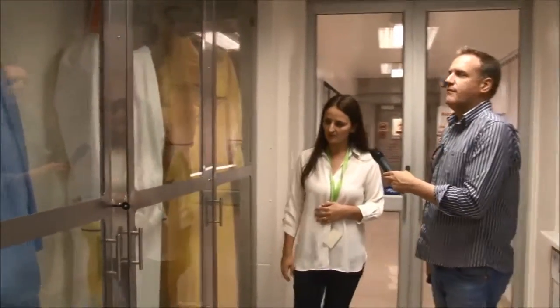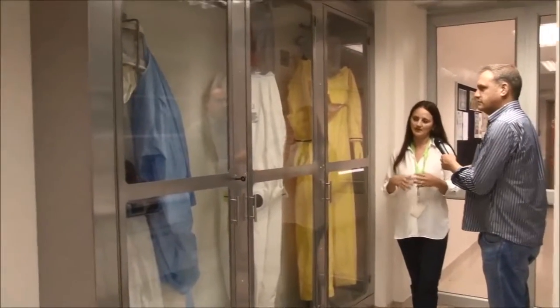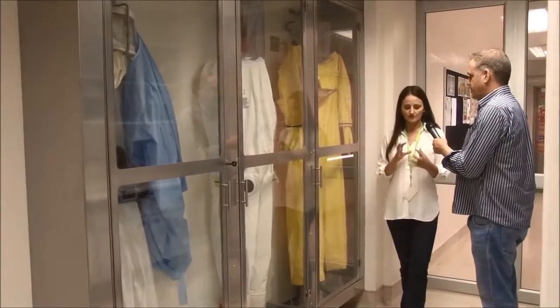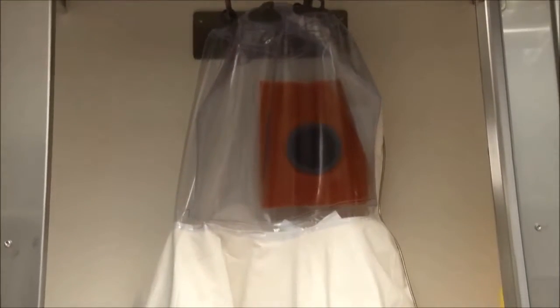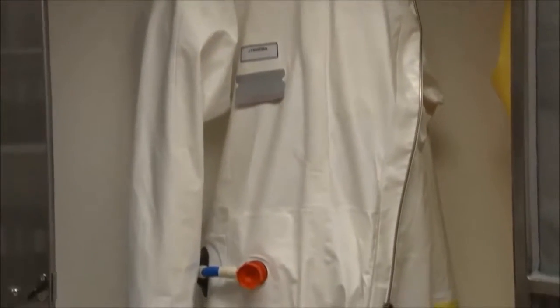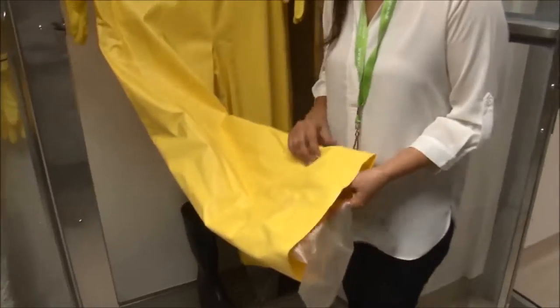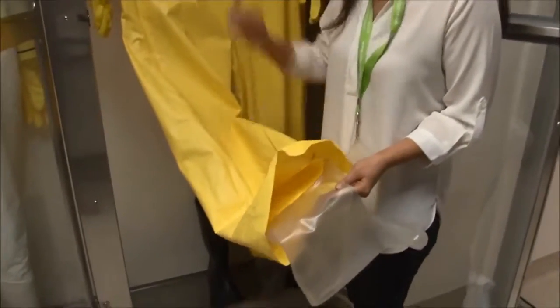Let's talk about these suits. If you want to work in a level 4 laboratory, you have to wear the right protective equipment. The laboratory itself provides what we call a biocontainment bubble — there's lots of engineering that drives the environment as well; it's not just the room. But you also have to wear protective clothing. We use fully enclosed plastic biosafety suits. When you zip these clothes, they're airtight — they should be airtight. You check the suit for any holes before you use it, and you actually sign off that you're happy to use the suit before you use it.